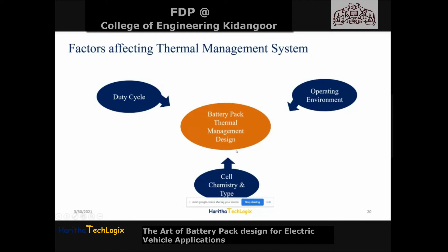The operating environment, whether the battery pack works in a closed or open environment, and the duty cycle, whether it runs 24/7 or 8 hours per day, determine the thermal management requirements depending on the usage profile. Depending upon the cell chemistry selected, it might or might not need a thermal management system, since some cell chemistries have a very high temperature withstanding capacity. Those chemistries can use just natural air cooling without a dedicated thermal management system. So cell chemistry is also one more deciding factor.